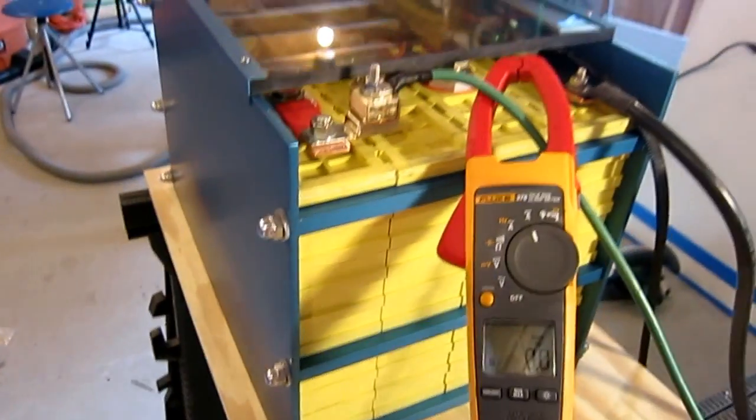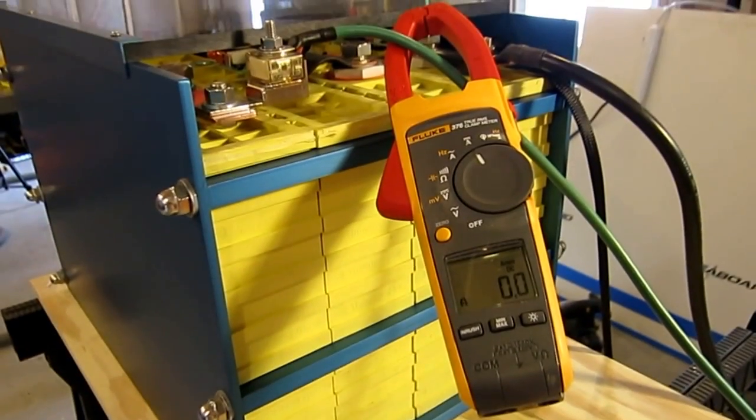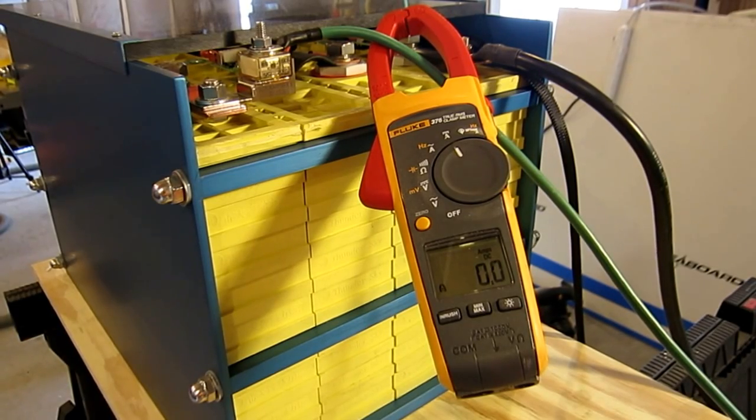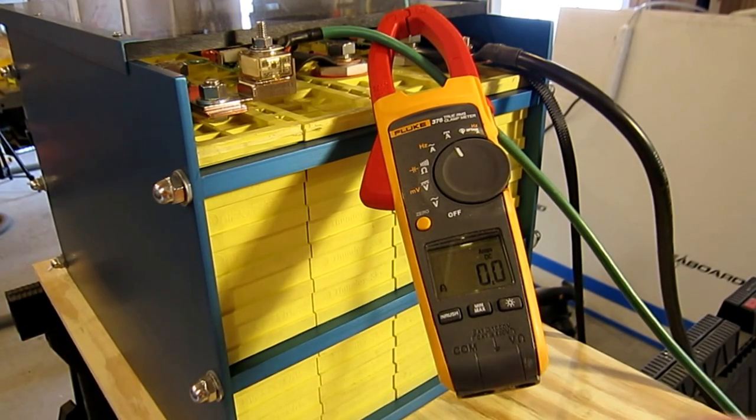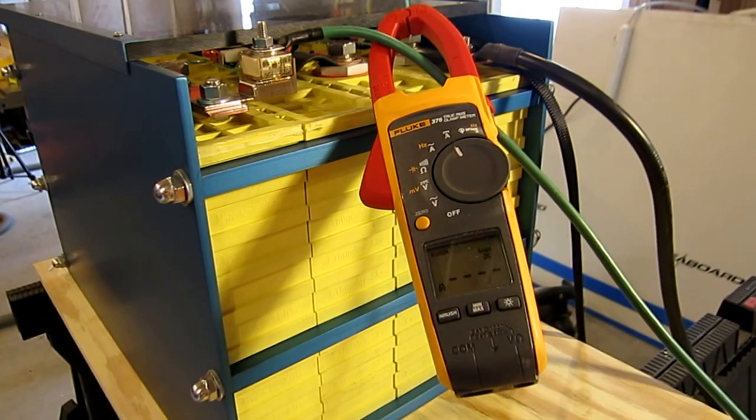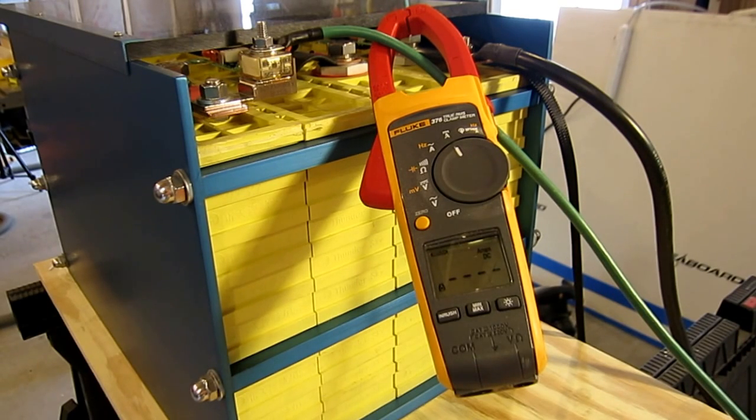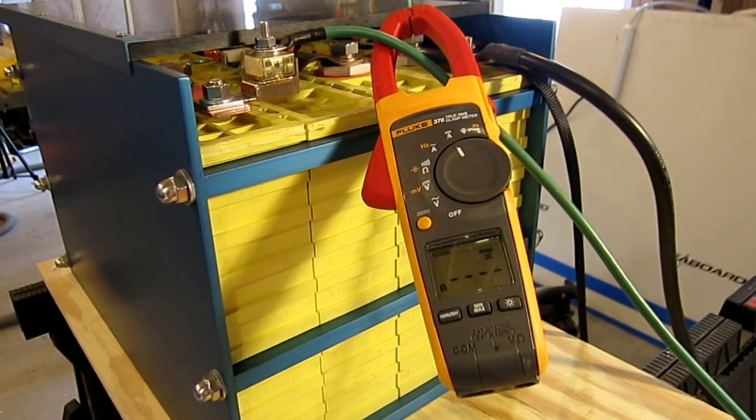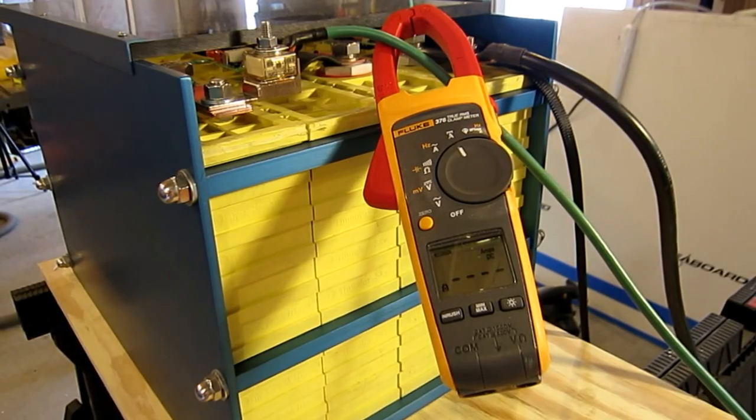You guys are going to see this for the first time when I see it. But I have shorted other fuses before, so I have a rough idea of what's going to happen. I'm going to set my Fluke meter to inrush current so hopefully it'll capture what kind of current we see. I'm going to have my wire cutters in hand just in case I need to snip that. I am going to simply flip the battery switch here. One, two, three.